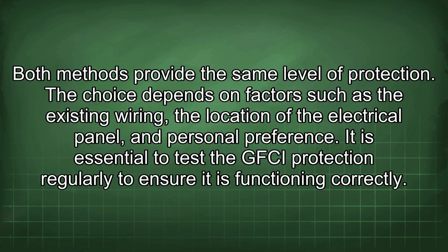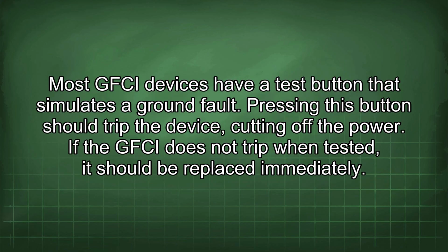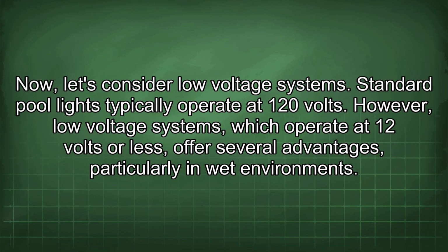It is essential to test the GFCI protection regularly to ensure it is functioning correctly. Most GFCI devices have a test button that simulates a ground fault. Pressing this button should trip the device, cutting off the power. If the GFCI does not trip when tested, it should be replaced immediately. Now let's consider low voltage systems. Standard pool lights typically operate at 120 volts. However, low voltage systems which operate at 12 volts or less offer several advantages, particularly in wet environments.